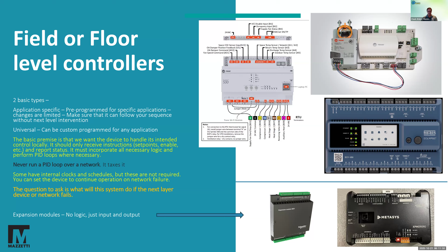So one of the things you want to know when you're designing a system is what happens if you lose communication. Typically I want an entire system that's going to be off one controller. It's making all the decisions, it's providing all the logic. I'm telling it what I want it to do, but if for some reason it loses communication with me and my computer, I want it to keep doing what it's designed to do.